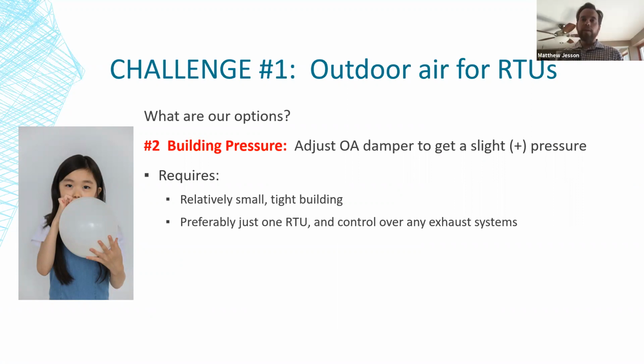What you need for that to work, first of all, you need to have a pretty small building that's tightly built. Obviously, trying to pressurize a space with 1 RTU, and if it's a big box store or something, that's not going to be feasible. So you want it to be pretty small, and preferably just 1 RTU system, so you don't have anything interacting with it.